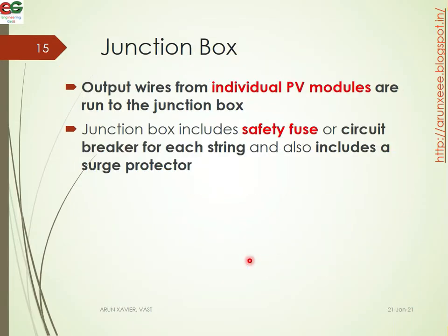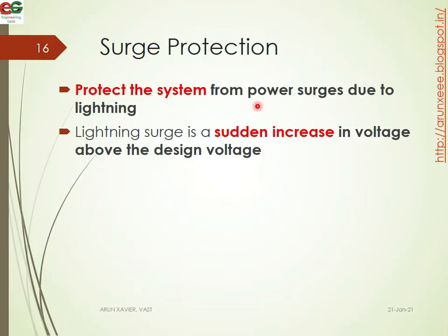Output wires from the individual PV modules are run into a junction box. The junction box includes safety fuses or circuit breakers for each string, and also includes surge protectors. Surge protection protects the system from power surges due to lightning. A surge is a sudden increase in voltage above a certain threshold level.